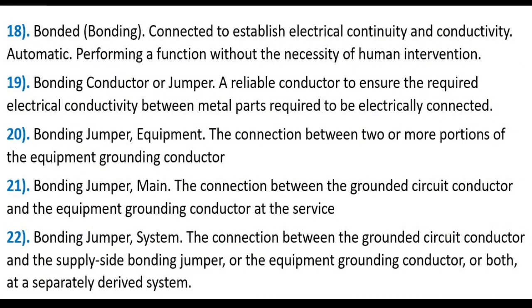18. Bonded/Bonding: Connected to establish electrical continuity and conductivity. 19. Bonding Conductor: A reliable conductor to ensure the required electrical conductivity between metal parts required to be electrically connected. 20. Bonding Jumper Equipment: The connection between two or more portions of the equipment grounding conductor. 21. Bonding Jumper: The connection between the grounded circuit conductor and the equipment grounding conductor at the service. 22. Bonding Jumper: The connection between the grounded circuit conductor and the supply-side bonding jumper, or the equipment grounding conductor, or both, at a separately derived system.